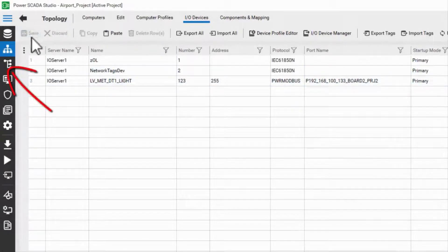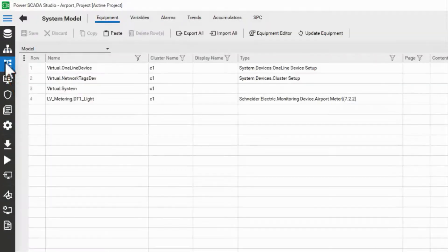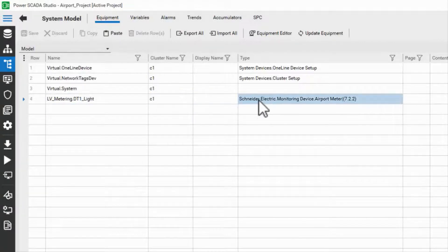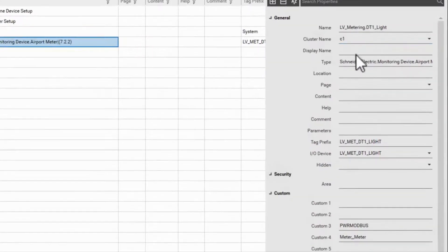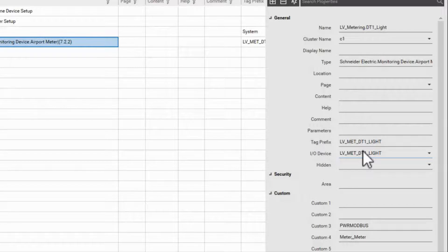The next database to see is equipment under the system model. Here is the device I added, and the type is its profile, which is a useful troubleshooting tool for verifying devices were added correctly. There are a number of other fields here used in various places, but note that the equipment record points to a single I.O. device. In another video, we'll look at a situation where we have multiple equipment referencing the same I.O. device.